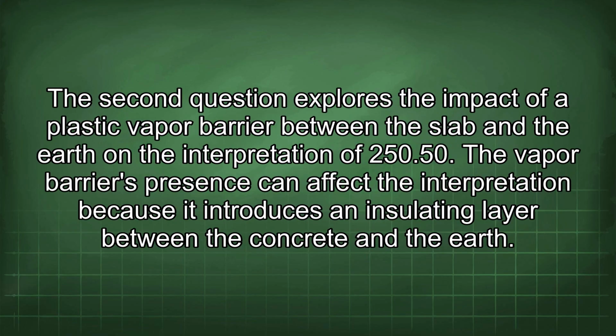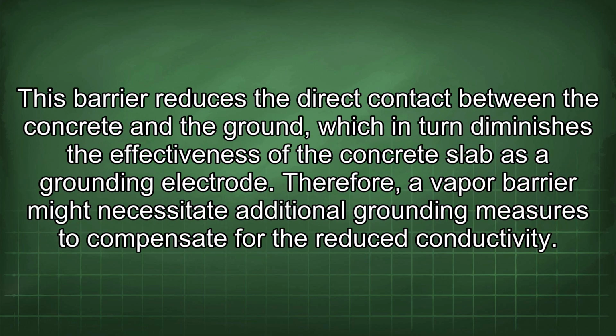The second question explores the impact of a plastic vapor barrier between the slab and the earth on the interpretation of 250.50. The vapor barrier's presence can affect the interpretation because it introduces an insulating layer between the concrete and the earth. This barrier reduces the direct contact between the concrete and the ground, which in turn diminishes the effectiveness of the concrete slab as a grounding electrode. Therefore, a vapor barrier might necessitate additional grounding measures to compensate for the reduced conductivity.